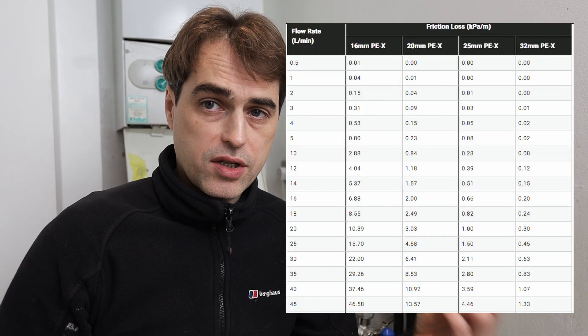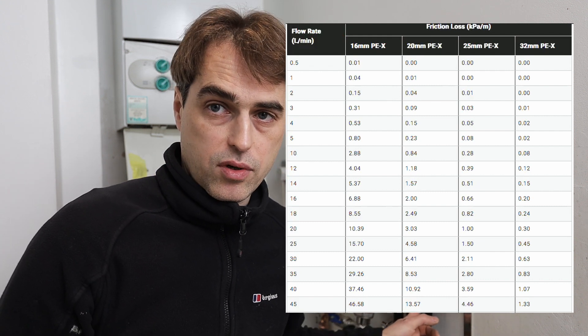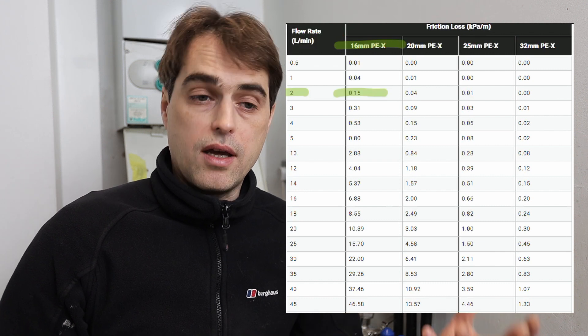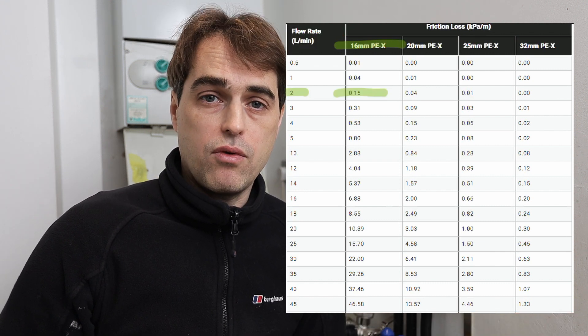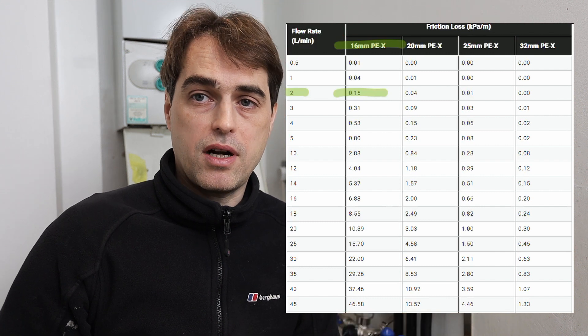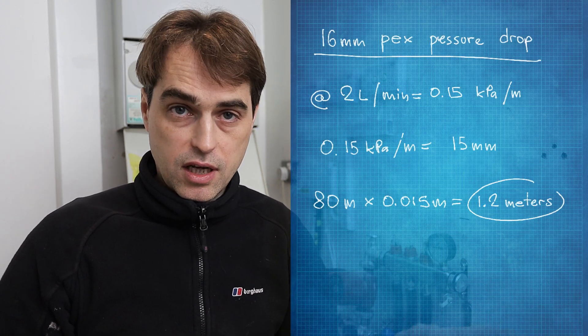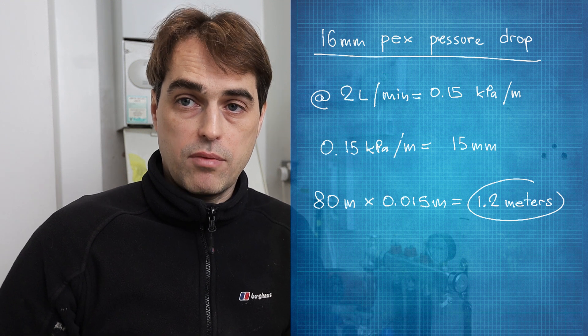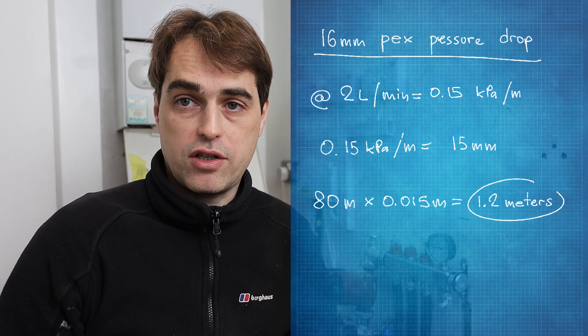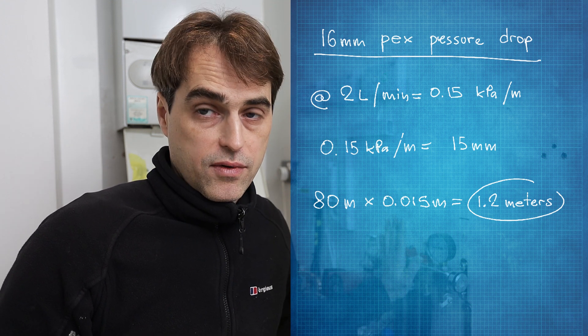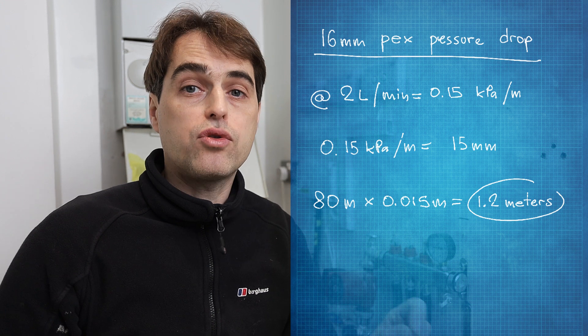Now we need a chart showing the pressure drop through 16mm PEX pipework at a flow of 2 liters per minute. The pressure drop through 16mm pipework at that flow is 15 millimeters per linear meter. Multiplying 15mm by the 80 meters of pipework gives 1200mm, or 1.2 meters pressure drop. That's our index circuit for this manifold and the pump has to overcome a resistance of 1.2 meters.